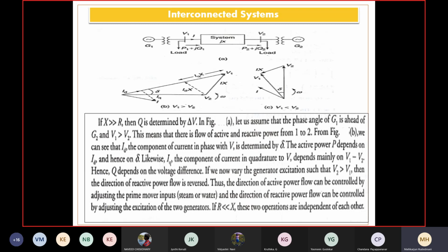How does that reactive power flow occur from bus 1 towards bus 2? When is that? And bus 2 towards bus 1? When is that? So that's what excitation control is: such that V2 is dominating over V1, then the direction of the reactive power is reversed. So the direction of active power can be controlled by adjusting the prime mover. This is very interesting. When we see P balance, it is adjusted by mechanical supplement of the turbine, which will enhance its mechanical power so that the electrical need is worked out.